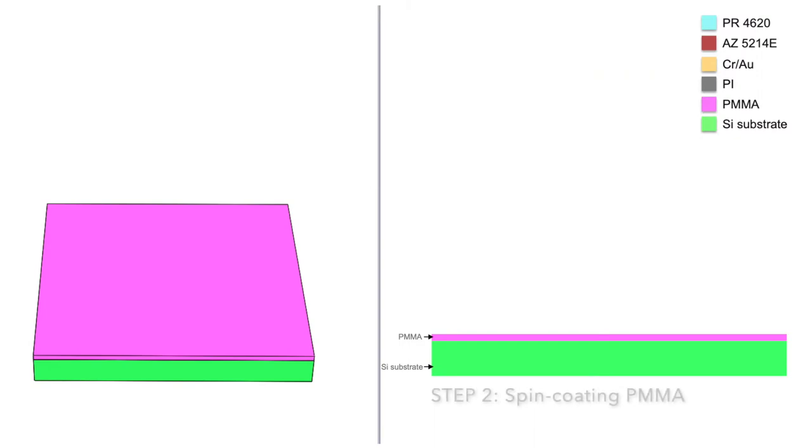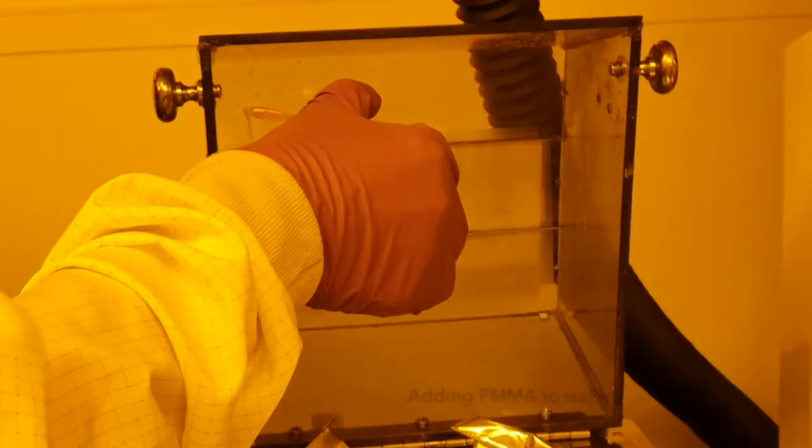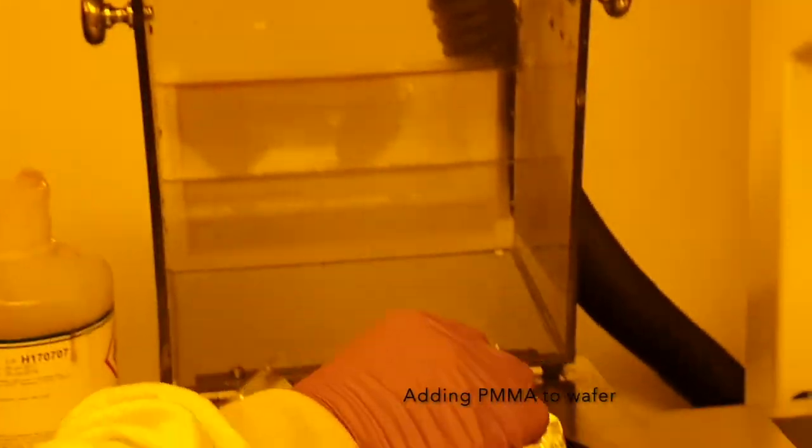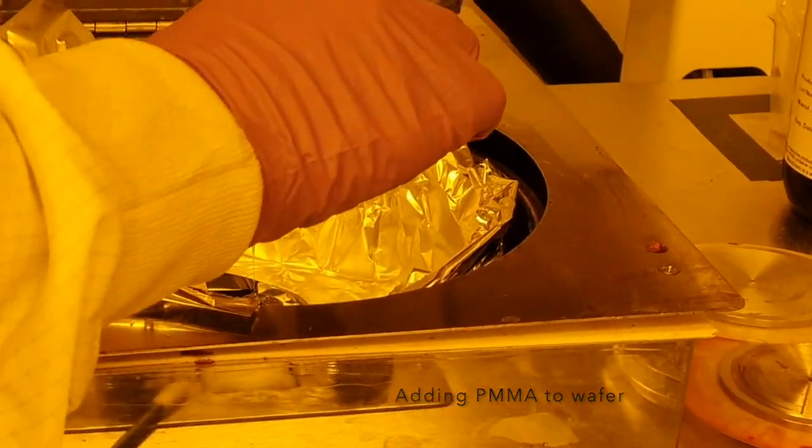Next, we spin coat a layer of PMMA as a sacrificial layer which will be used to release our device from the rigid silicon substrate once the sensor is ready. We place the sample in the spin coater and use a sequence of variable spin speeds in order to achieve a uniform thickness.